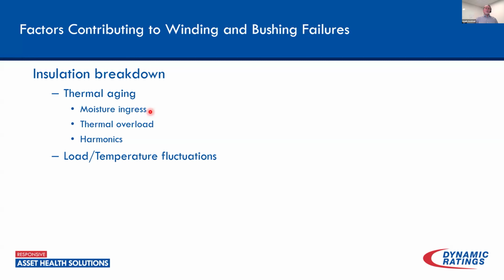As we go through those temperature and load fluctuations, the oil is expanding and contracting. As that's occurring, we may be pushing dry air or nitrogen out of that transformer, and then giving an opportunity to suck in moist air. Of course, when it comes to overloading and thermal aging, overloads are going to have a significant impact. So if we're overloading our transformer and not managing our cooling properly, any type of thermal condition is going to cause increased thermal aging.